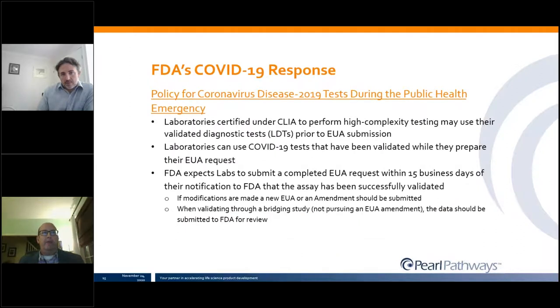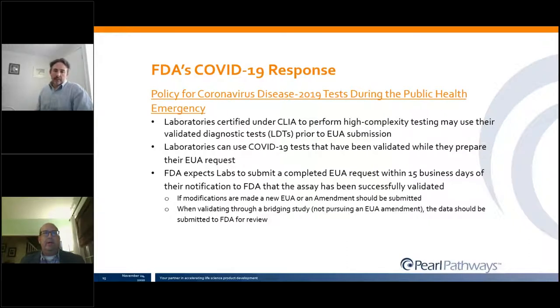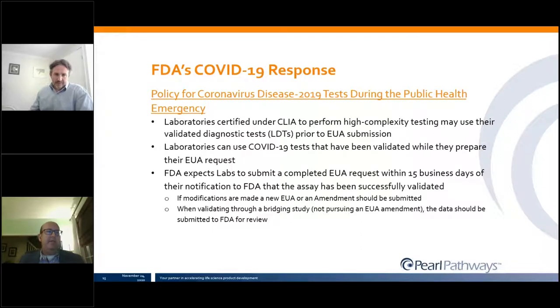FDA also put out a policy on coronavirus disease 2019 testing for public health emergencies. This guidance provides details about laboratories providing laboratory-developed tests (LDTs) that support COVID-19 testing as part of an EUA submission. Laboratories can use their test if it has been validated under CLIA while they prepare their EUA request. However, FDA expects the lab to submit a complete EUA request within 15 days of being on the market after successful validation. If there are modifications to the LDT, a new EUA or amendment will need to be submitted, and bridging study data must be submitted to FDA for review.